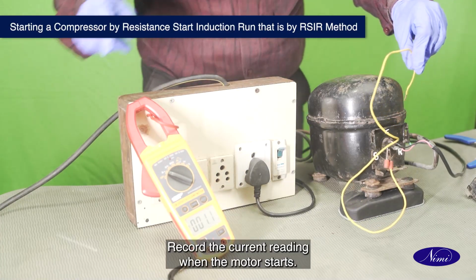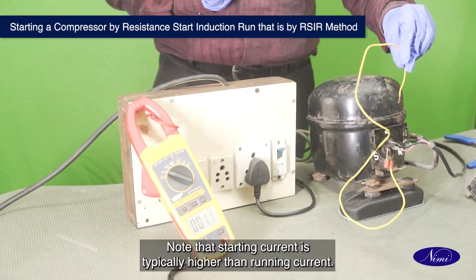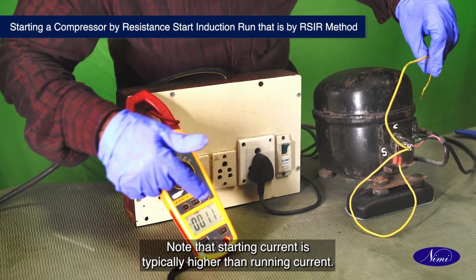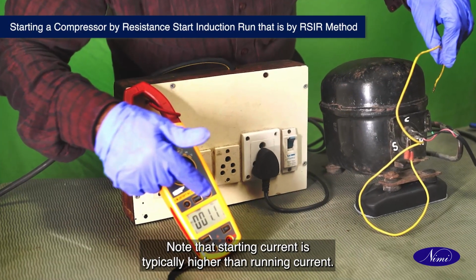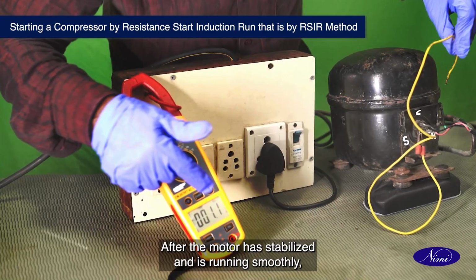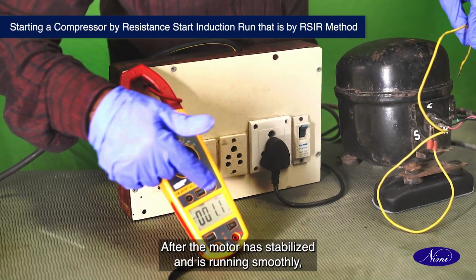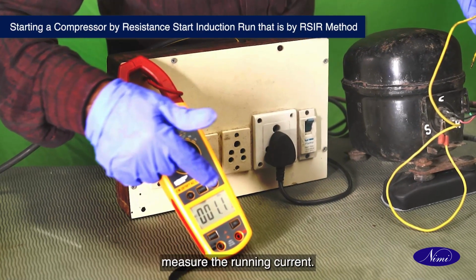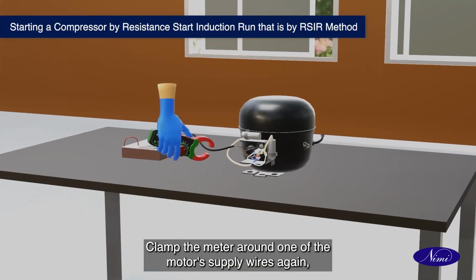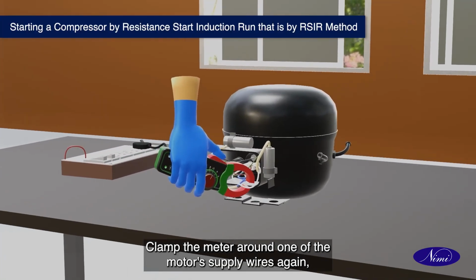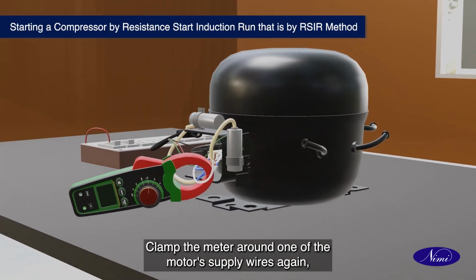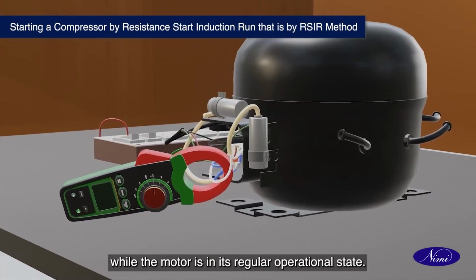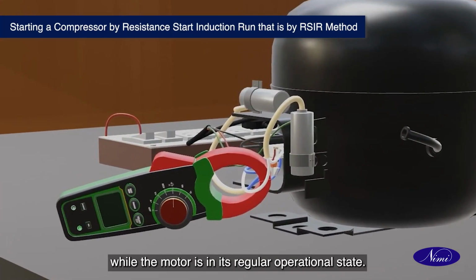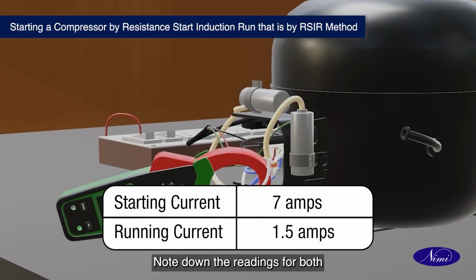Record the current reading when the motor starts. Note that starting current is typically higher than running current. After the motor has stabilized and is running smoothly, measure the running current. Clamp the meter around one of the motor's supply wires again, observing the current while the motor is in its regular operational state. Note down the readings for both starting and running currents.